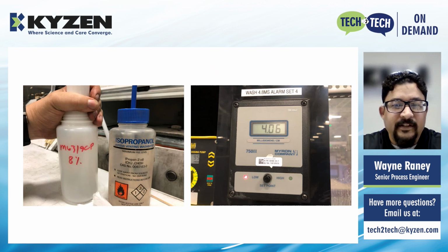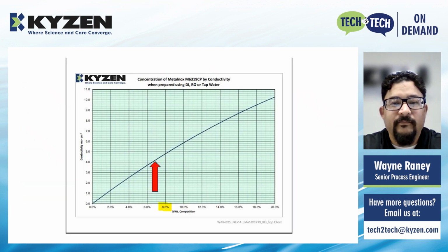We started by not cleaning the probe and measuring a premixed 8% concentration by weight. The customer said that 8% was their set point. We did a calibration check before we cleaned a probe and compared it to the chart. 4.06 millisiemens was the measurement as indicated by the red arrow, and it's just under 8% concentration as indicated by the yellow highlighted portion. An 8% concentration is supposed to read approximately 4.8 millisiemens. This conductivity is lower than expected, so we cleaned the probe and the conductivity actually came up to the proper value.